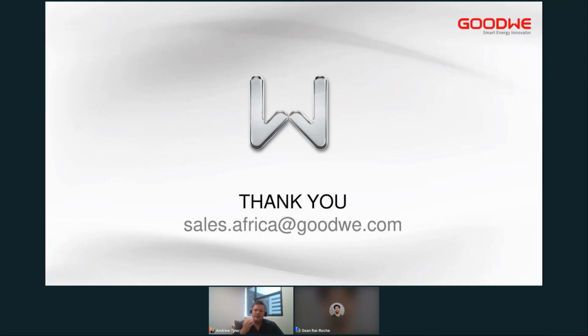But the main feature I would say is the smart load control. We're one of the pioneers in that space, and I think it's so important because whenever somebody's installing or looking at a residential system, the first point of call should always be, what can we do to try and reduce the load within this home? And whether it's changing the heat pump to a gas geyser or solar geyser, or typically with our system, you could also switch loads intelligently to make sure that they fall during your peak sun hours. But definitely an exciting product. We can't wait to see you guys install and hear your experiences.